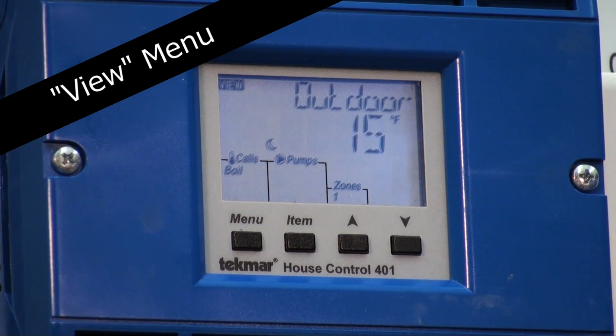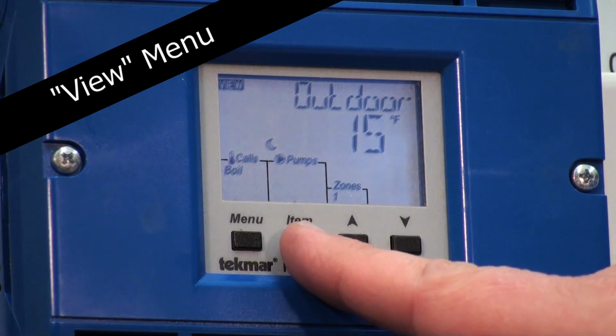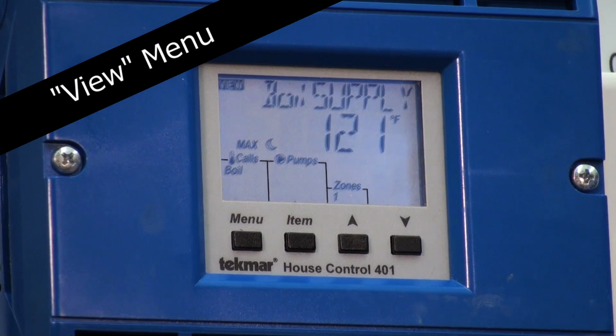And under View, now you want to press the Item button. Right now we're showing the outdoor temperature is 15 degrees outside. Press the Item button. Now you're going to see your boiler supply water temperature, what is currently being sent out of the boiler for your water temperature. If you press Item again, you're now looking at the boiler target temperature. This is what the boiler is targeting for delivered water temperature to your house based on outdoor temperature and indoor temperature feedback from our thermostats.